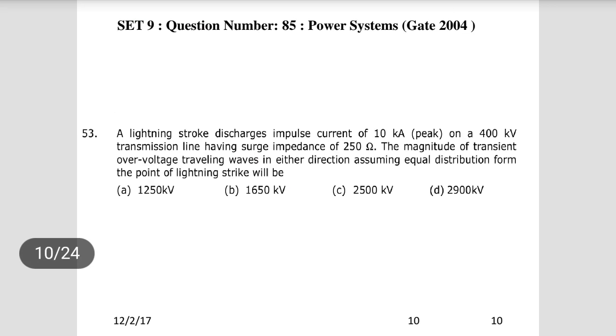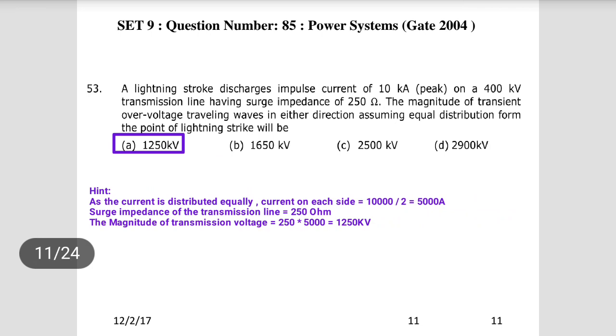Fifth question: a lightning stroke discharges an impulse current of 10 kilo-amps peak on a 400 kV transmission line having a surge impedance of 250 ohms. Find the magnitude of the transient overvoltage traveling wave in either direction, assuming equal distribution from the point of the lightning stroke. Since current is equally distributed, current on each side = 10/2 = 5 kA. Traveling wave voltage = 250 × 5 = 1250 kV.